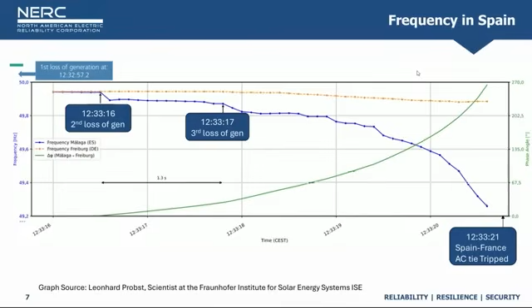So as you would expect, when you lose a unit, frequency goes down. And you lose another unit, frequency goes down. And then, of course, finally, they lost frequency and had to split from the system. Next slide, please. This is kind of a visual of how things went. Starting from the oscillations that occurred a half hour before the blackout, operators prioritized oscillation mitigation measures. They wanted to dampen those things out.